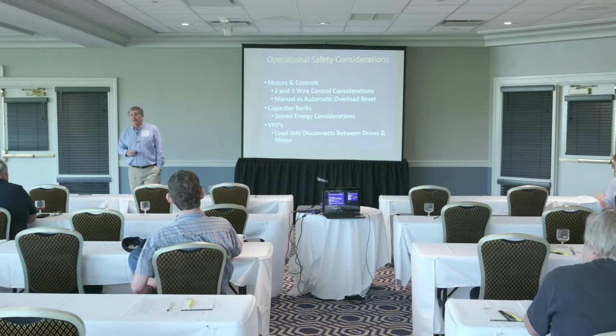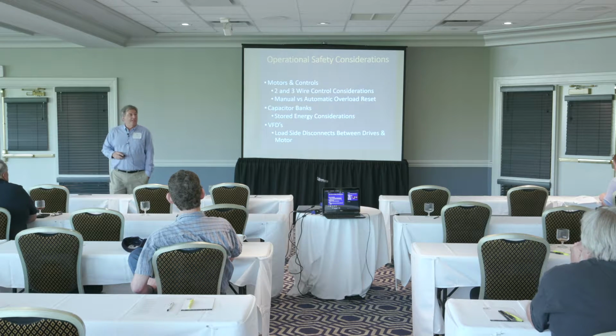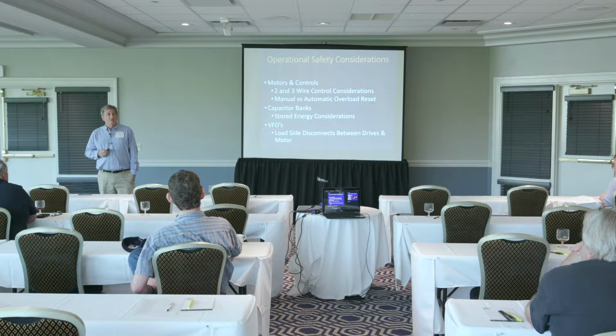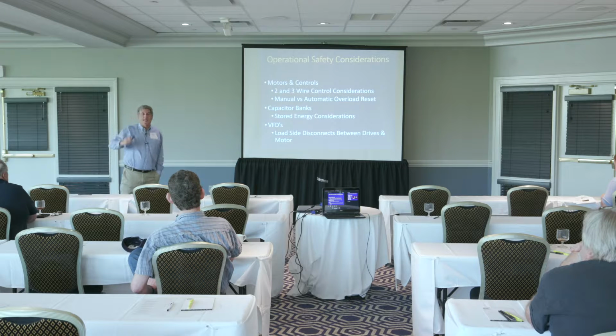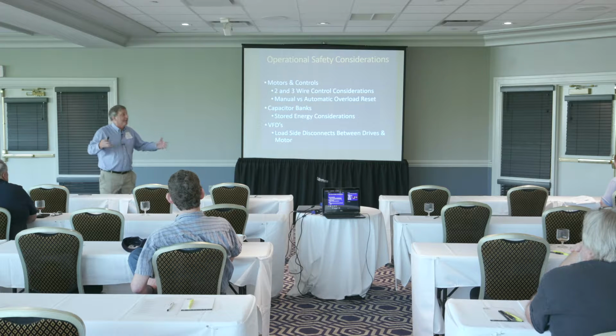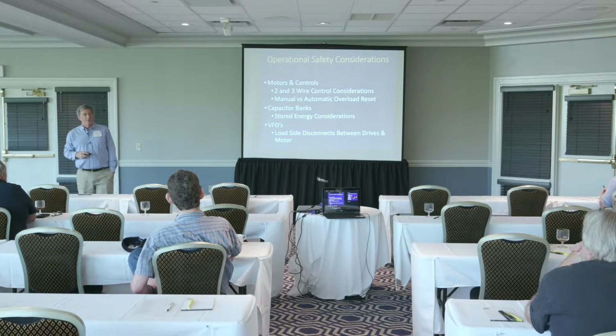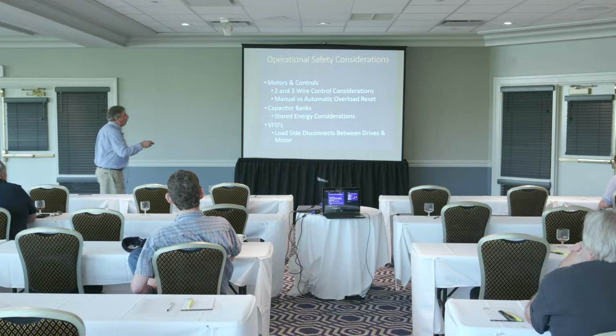Capacitor banks. We talked about power factor correction. Now I put a device into your facility that might be in your circuit or your main service that stores energy even after you flip the main disconnect before it. So now I have to make sure under my lockout tagout procedures that I remove stored energy from devices, which a capacitor will do. It will store energy. So now before I can work on equipment safely with lockout and tagout, what are the things I see that people sometimes forget about in removing that stored energy from the capacitor bank before they work on a system?